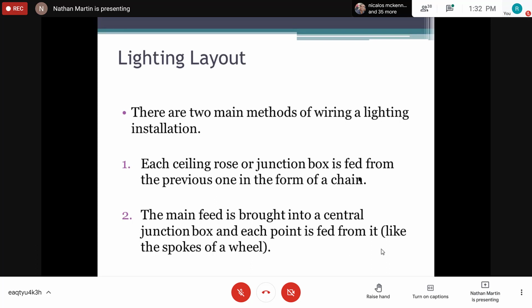So the main is brought into a central junction box, right? And then we go from that junction box to the different points, right? But again, this is the one that is mainly used because then we're talking about a large conduit in this type of installation, as well as the number of cables that can be pulled inside the conduit. Because if we're going to bring it to a point and then for every circuit, we're going to take it from this point, then we're talking about a larger conduit in the installation rather than looping from one box to the next. However, there are regulations that we must follow to tell us how many lights we can put on a particular circuit, right? And it all depends on the breaker that you are using, whether it be a 15 amp or a 20 amp breaker to control your light.